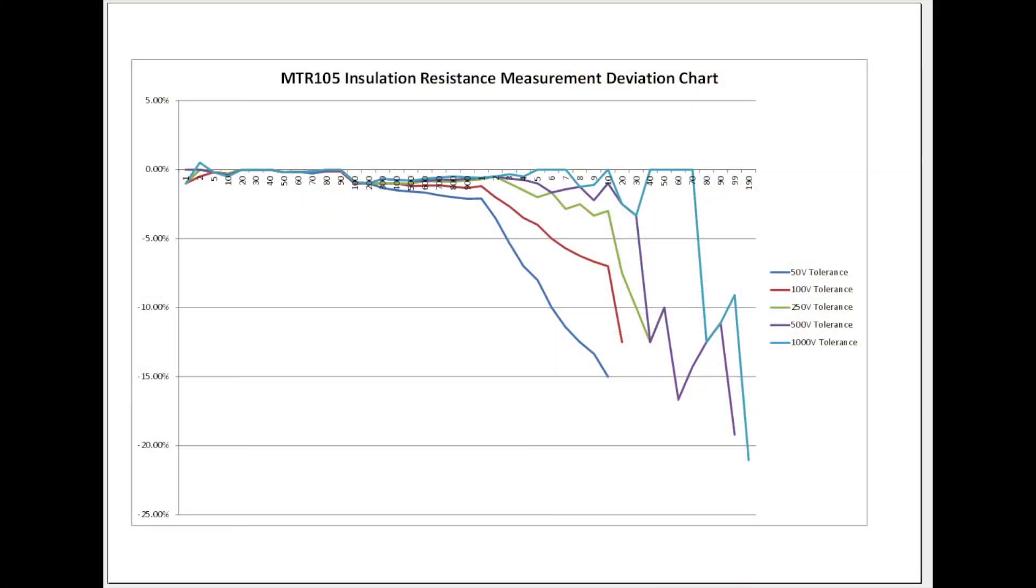Moving on to the plot, the plot tells the picture really. After one gig ohm on a 50 volt test you can see the tolerance starts to drop away and at 70 gig ohms for a 1000 volt test you again see the tolerance start to drift away from the nominal values.